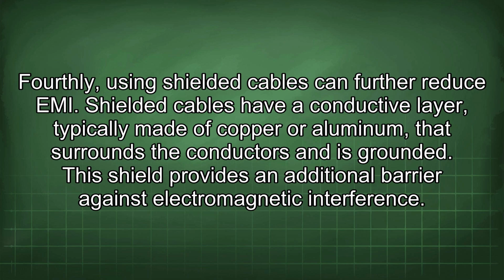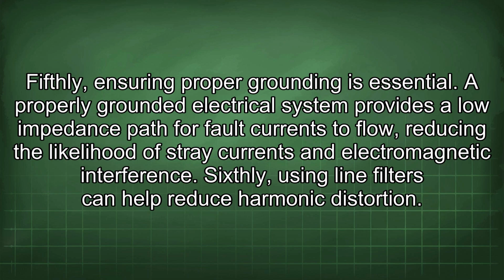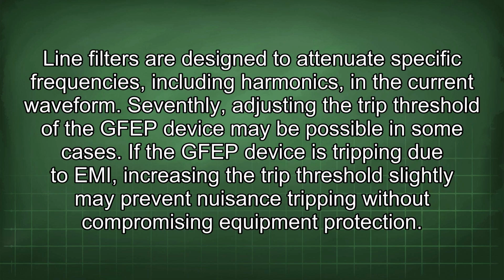Fourthly, using shielded cables can further reduce EMI. Shielded cables have a conductive layer, typically made of copper or aluminum, that surrounds the conductors and is grounded. The shield provides an additional barrier against electromagnetic interference. Fifthly, ensuring proper grounding is essential. A properly grounded electrical system provides a low impedance path for fault currents to flow, reducing the likelihood of stray currents and electromagnetic interference. Sixthly, using line filters can help reduce harmonic distortion. Line filters are designed to attenuate specific frequencies, including harmonics, in the current waveform.